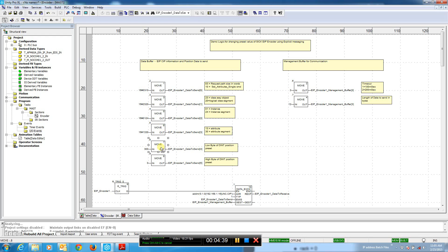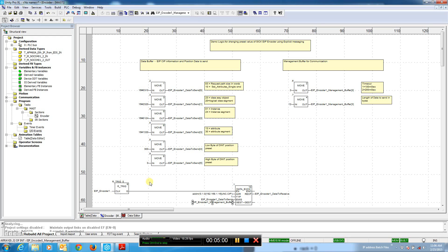The extra two bytes are going to be the low byte of the DINT for the position preset. In this case, we're going to set the encoder to 300, and the high byte we're leaving at zero. So you can see the instruction — here's the data to send and here's the actual management buffer itself. When we execute a data exchange, we just want it to be a trigger, so we're going through an R trigger, which is a positive pulse transition.